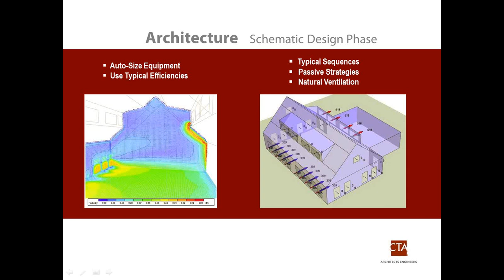So you get some of that natural ventilation effect. When we're talking about naturally ventilating a building, it's sometimes hard to figure out. ASHRAE 62.1 has some standards for how big your opening has to be for a certain floor area, or you can calculate it on your own. This IESVE software will do that. It gives you your natural ventilation through each of these windows at different wind speeds. So maybe your openings don't have to be quite as big, and you can look at whether it really will work for you.